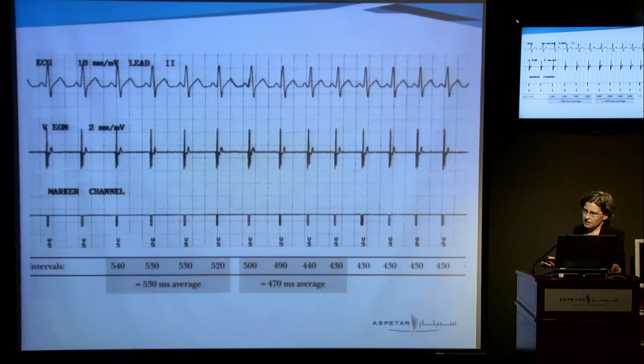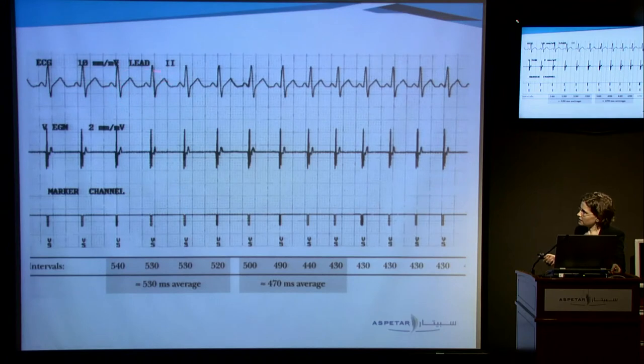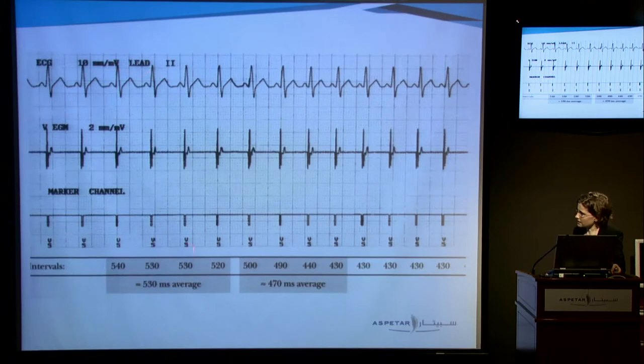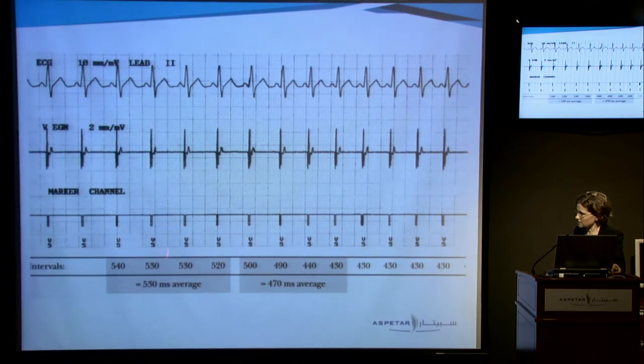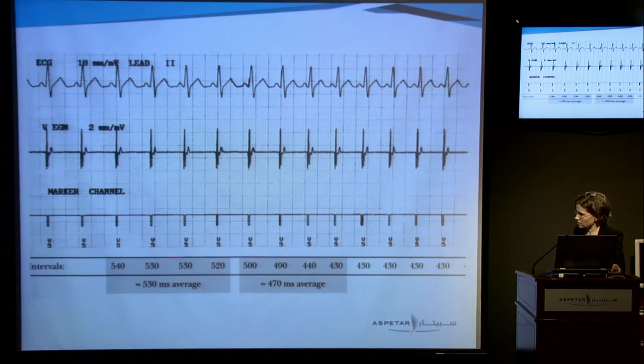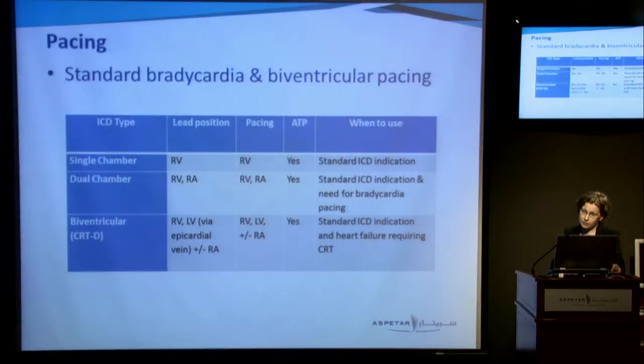But how does the ICD know whether the patient's in VT? It's all based on calculations. The ICD calculates the RR interval — essentially the heart rate — and this is called the cycle length, measured in milliseconds. The marker channel shows VS (V-sense), meaning it's sensing a ventricular complex, and it calculates the interval between each complex so that it knows the heart rate.